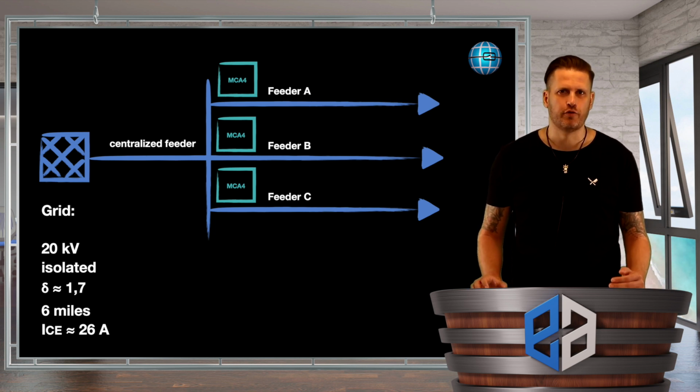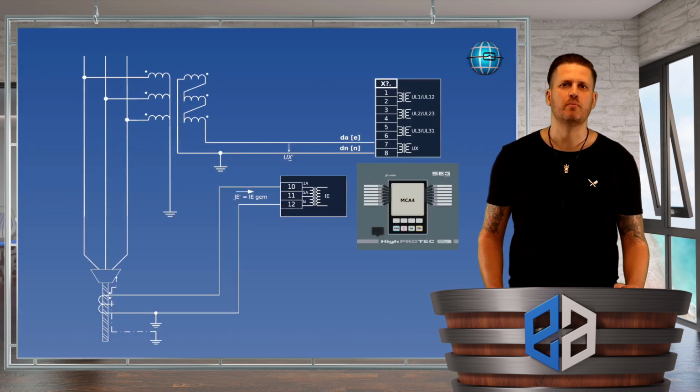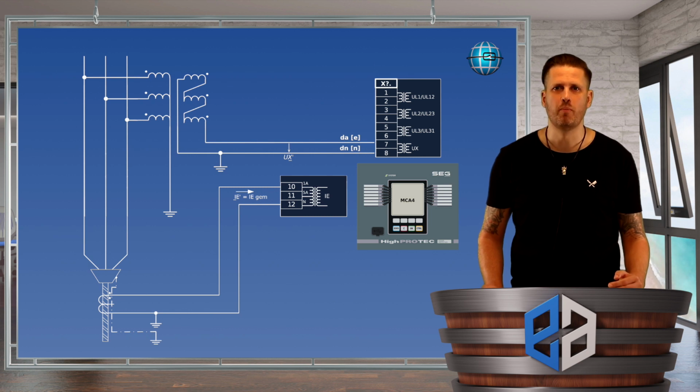The present network configuration results in the selection of the sinus phi method as the protection algorithm, and we have implemented our protection system as follows. On the secondary side, we measure the triangular windings of our 3 voltage transformers connected in an open triangle to get our voltage, and the zero current will be measured with a 60 to 1 amp split coil transformer.